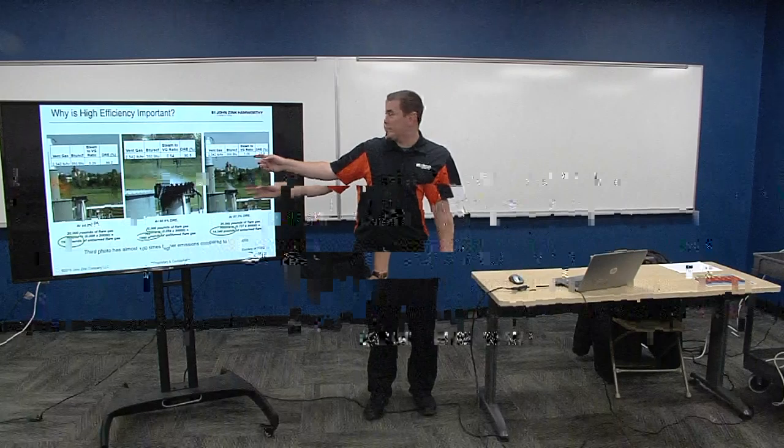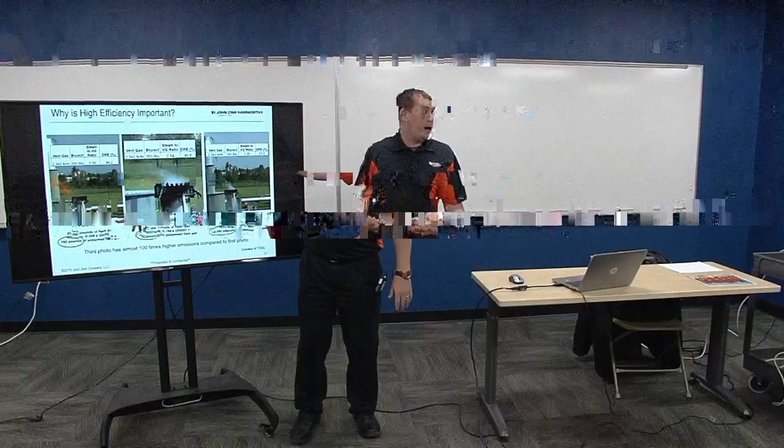Well, this is the way most people were operating their flares, right? At a steam to vent gas ratio of one, which is really not bad, so people used to think, right? But the efficiency of it was 27%. That's a lot of hydrocarbon being released, right?